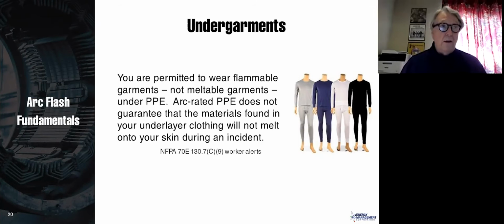But they will say if you have a 12-calorie piece of gear that you're working on and you're wearing PPE that's rated for 12 calories, they will protect you from a second-degree burn unless you are wearing meltable garments under those PPE. And in that case, you could get a third-degree burn, even though it's a 12-calorie piece of equipment and you're wearing 12-calorie PPE, because they will not guarantee you that that underwear couldn't melt. And if it melts, you're pretty much going to get a third-degree burn.